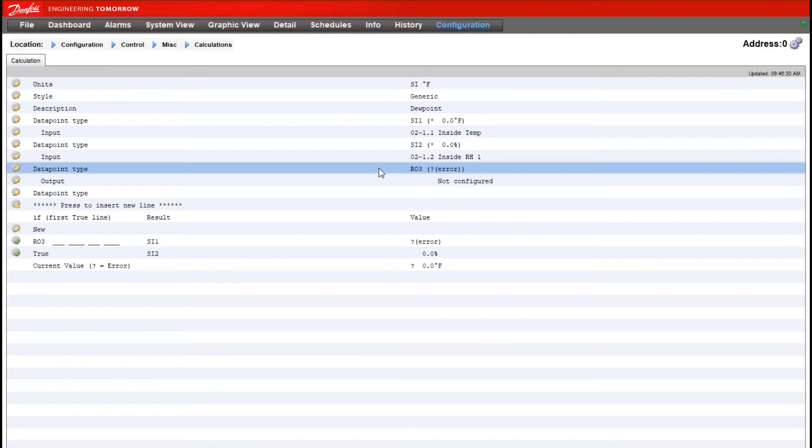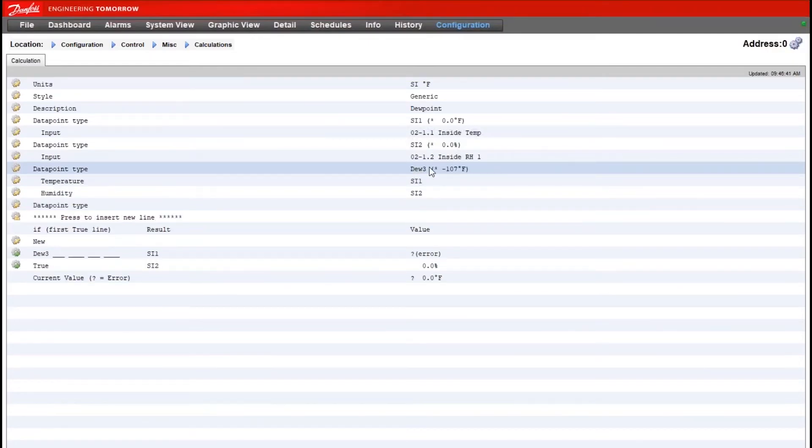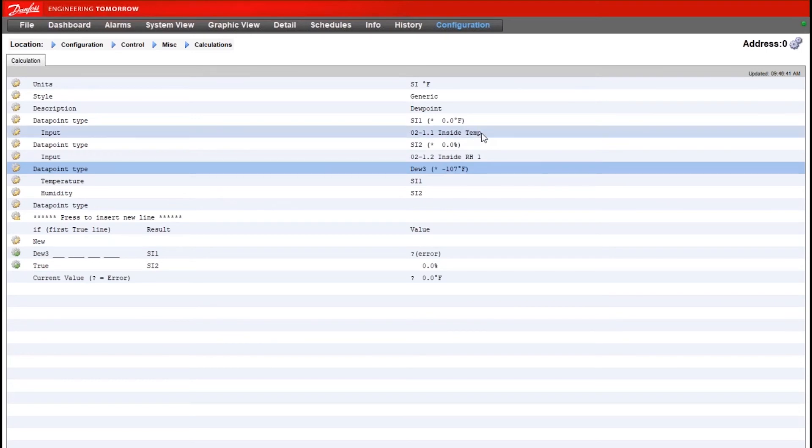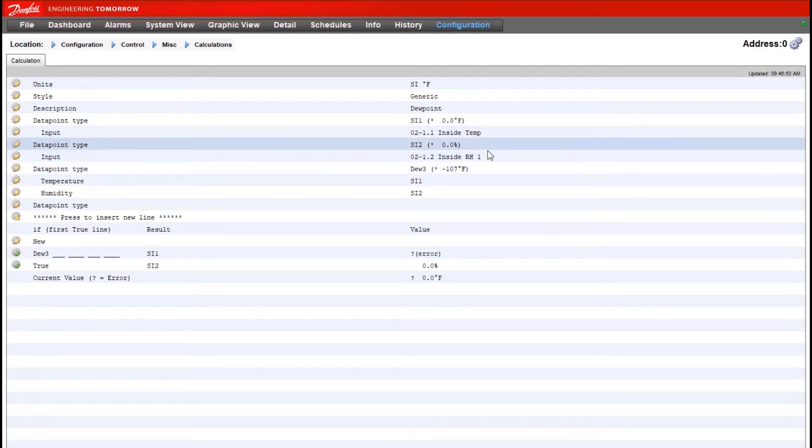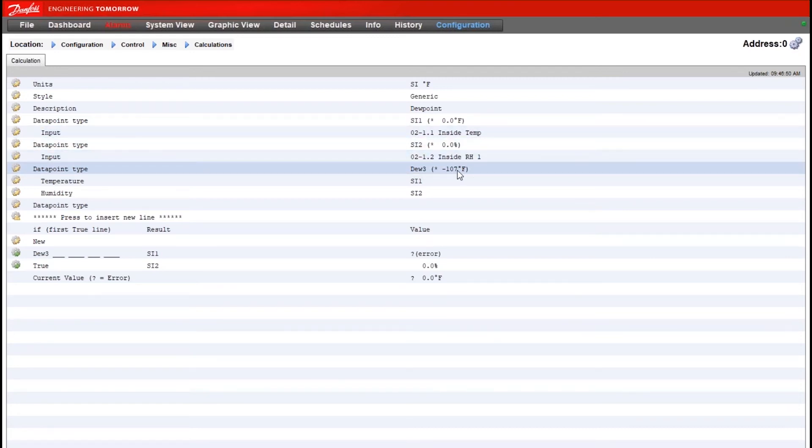For our third data point type, now you will see an option here for dew point, and the catch there to keep in mind is that we need to have a temperature sensor and a humidity sensor already configured to see that option for dew point. If we haven't set these first two up already, the third data point type for dew point won't appear as an option.